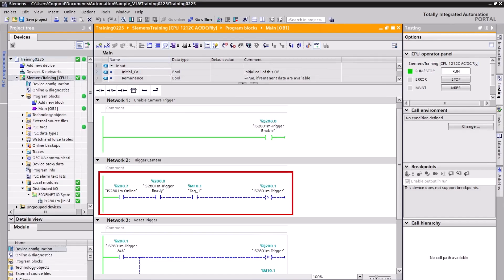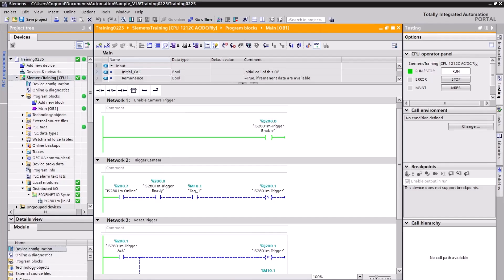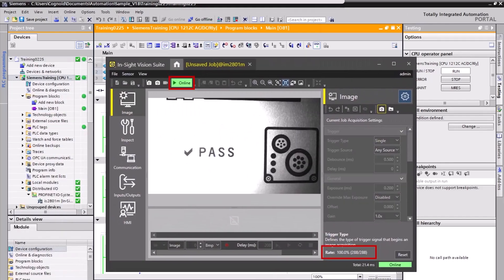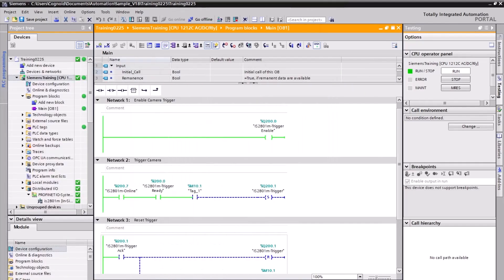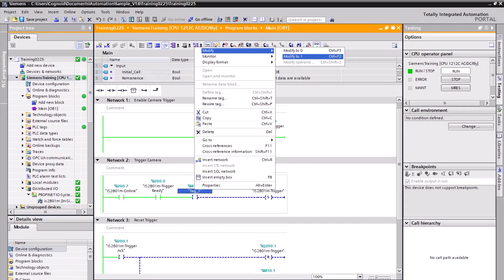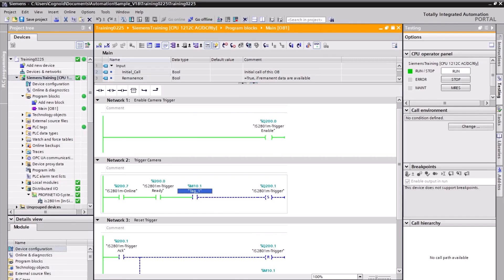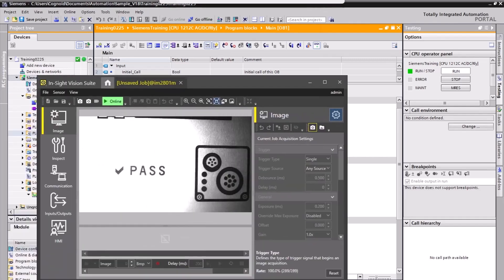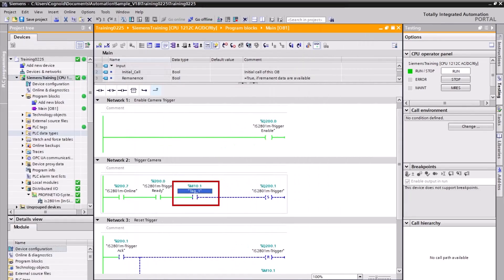Notice the change in the green lines. Since the camera is not online, the power flow stops at the online instruction. Open InSight Vision Suite and click the Online button to put the camera online. Right-click the memory bit tag on rung 2, select Modify, then Modify to 1 from the fly-out menu. You have successfully triggered your camera using the PLC. Move the part in the camera's field of view and repeat this step to manually trigger the camera again.